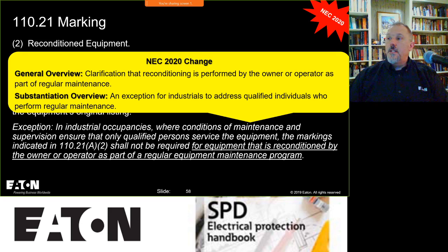So the exception basically looks at industrial occupancies where conditions of maintenance and supervision ensure that only qualified persons service the equipment. So you may be doing something in your heavy industrial that meets the definition of reconditioned, but because you're in a heavy industrial with conditions of maintenance and supervision and qualified persons, they give you the exception so you don't have to worry about A2 with regard to labeling, marking, and equipment reconditioned by the owner or operator as part of a regular equipment maintenance program. That's an exception for the industrials. That's a little bit different environment.